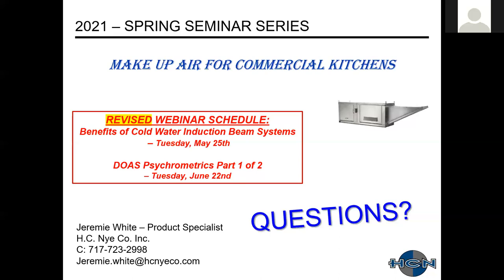Yeah. For the back supply option, how does this work with utility routing on the backside of the appliances? Good question. It does not work that well. I have seen manufacturers route stuff through the makeup air plenum, but the big thing with that is you're getting into a utility chase and then trying to introduce air through that utility chase, which is never really effective. So they would have to route those utilities around. That was a big sticking point for a lot of kitchen designers with that back return, having to deal with those utilities and move them around.